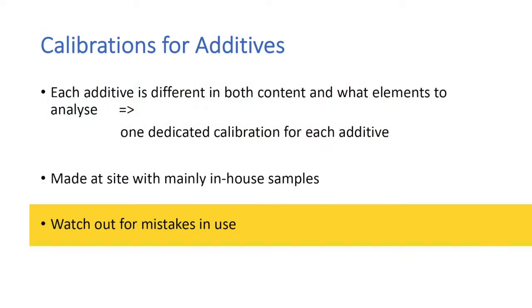But now in the corona time, we had manganese sulfide, and sometimes there was a very strange result. And when I came into the office and went to the machine and looked, there was one lab technician who had used the wrong calibration. The low alloy calibration had manganese in it, so he or she had run it with the low alloy calibration. Everyone was just like, big question mark, why some samples got very strange manganese results. So that's what I'm meaning, watch out for mistakes in use.